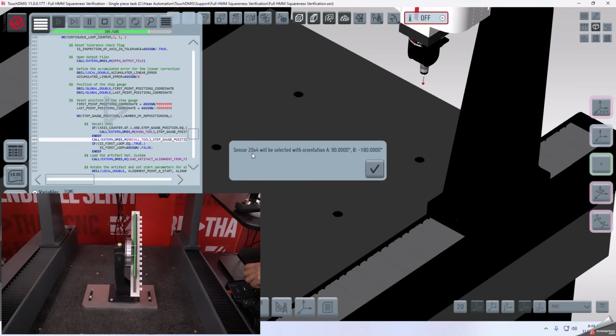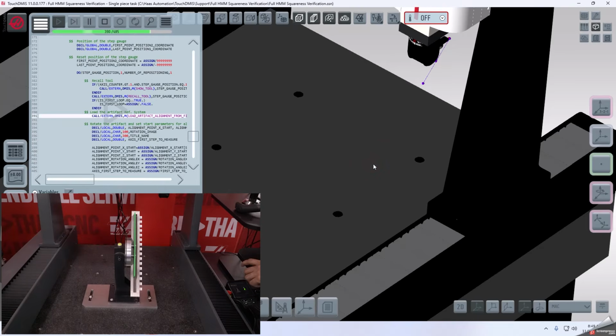TouchDMIS will remind us to make sure that the 20 by 4 millimeter ruby ball is installed on our probe, and that is in the A90 and B-180 orientation. Then I will click on the check mark. Now we will continue following the instructions on the screen. We need to unbolt the fixture from the base plate and rotate the fixture clockwise 90 degrees for the XZ position 1 measurement routine. And I'll do that now.